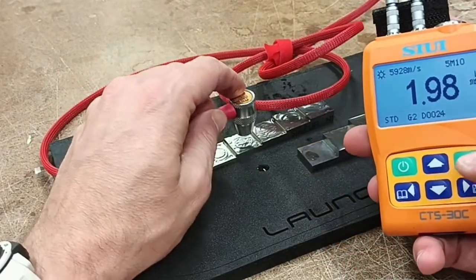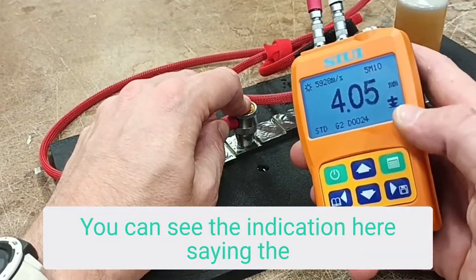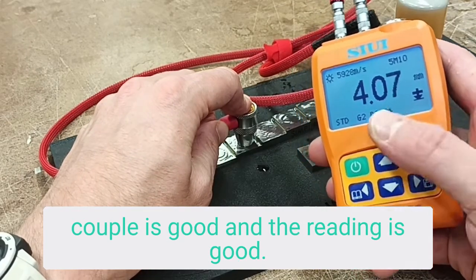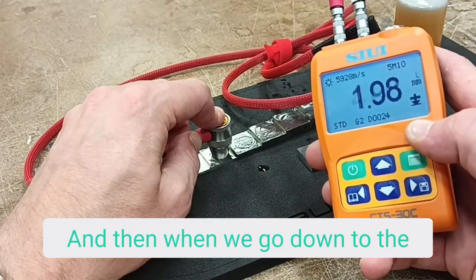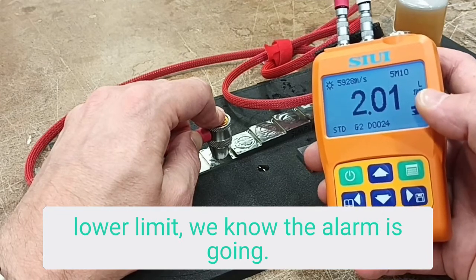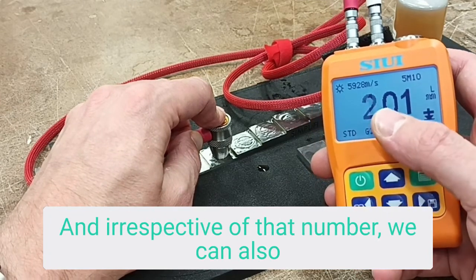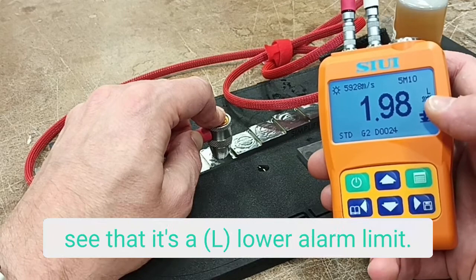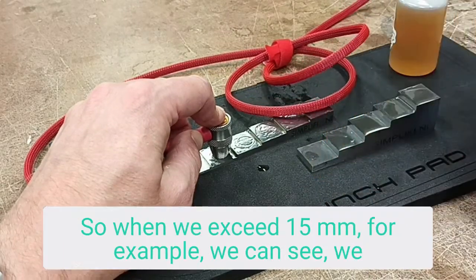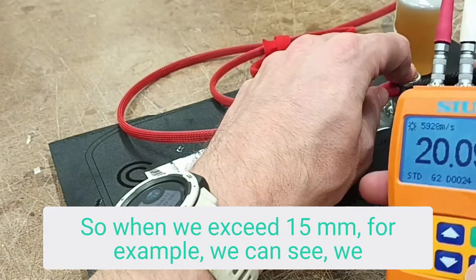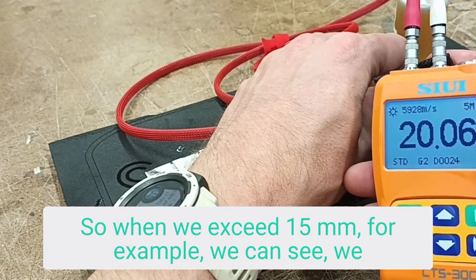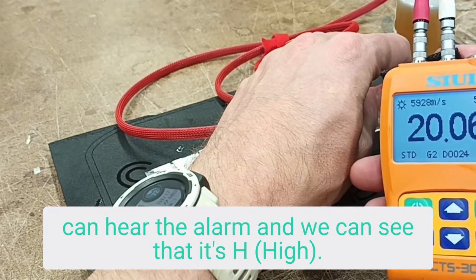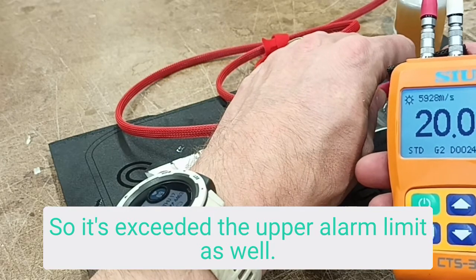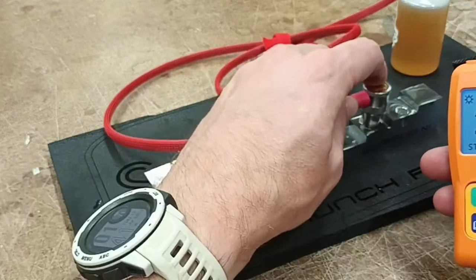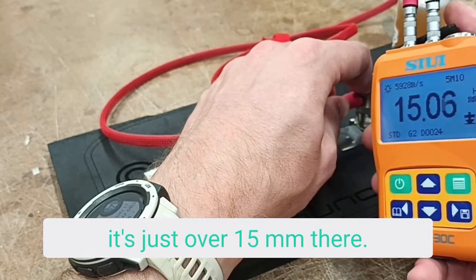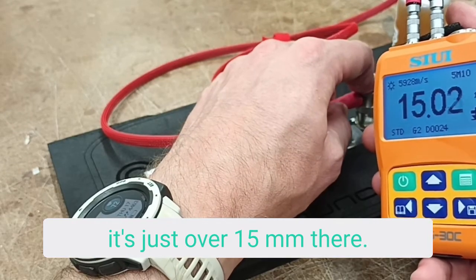You can also see the indication here saying the coupling is good and the reading is good. And then when we go down to the lower limit, we know the alarm's going, and irrespective of that number, we can also see that it's a lower alarm limit. So when we exceed 15mm, for example, we can hear the alarm and we can see that it's H, so it's exceeded the upper alarm limit as well. It might do the same because it's just over 15mm there.